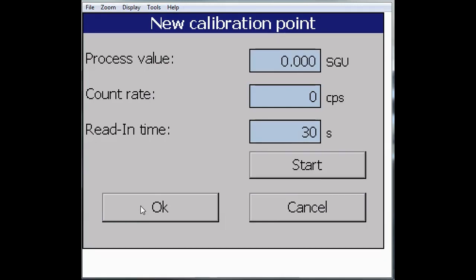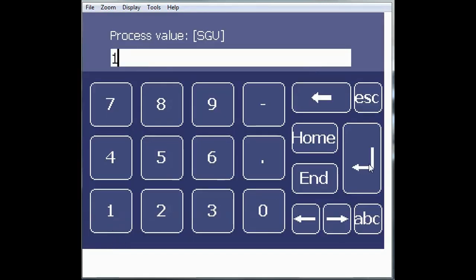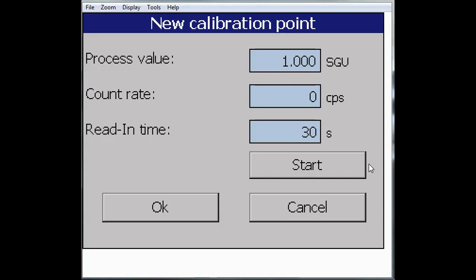If your product is a known density such as water and not changing, simply enter the density. If the density does change of your product during the process, you'll want someone to be taking a sample at the exact time that you're reading in the counts on the gauge. Once they return with a value for that sample, you will enter it specifically into the process value. For our example, we're running water. So I'll click the Start to begin the read-in.